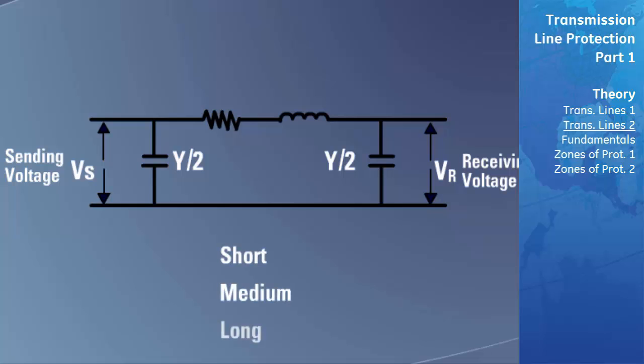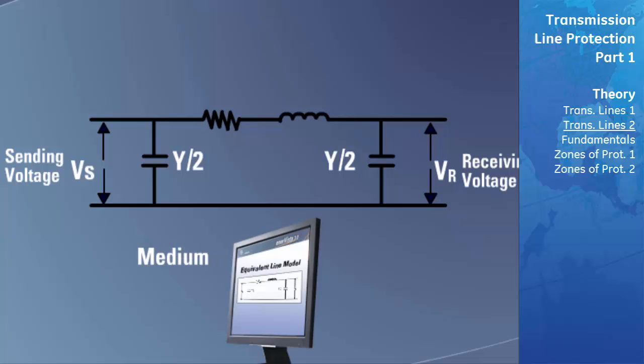The PI model shown here was historically used by the protection engineer to represent medium length lines. However, by using this representation of the line in addition to computer-aided software now readily available, the protection engineer can accurately calculate all required values for both medium and long transmission lines. This data simplifies the protection engineer's task in performing fault calculations to set up the distance protection within a relay.